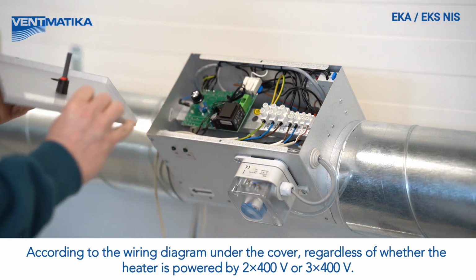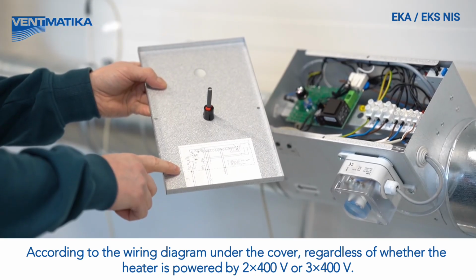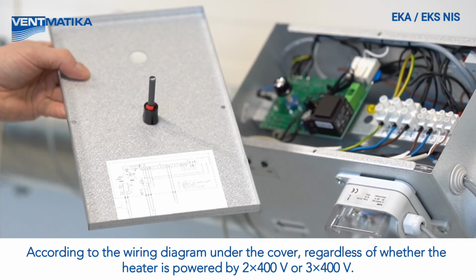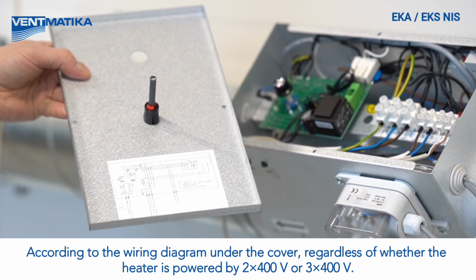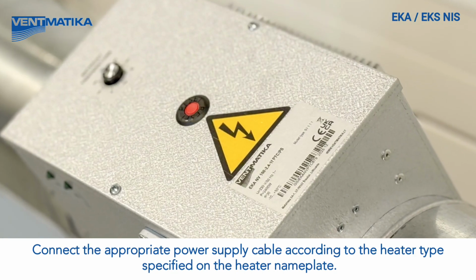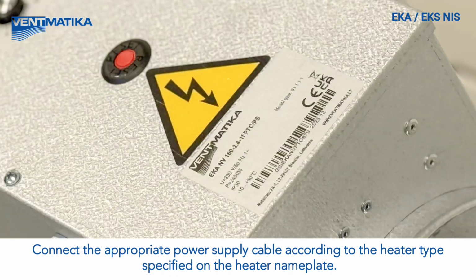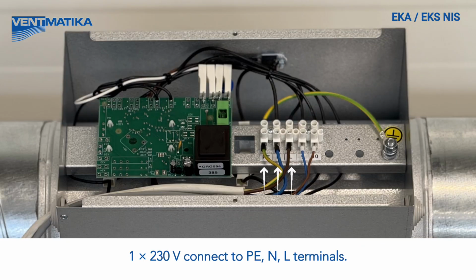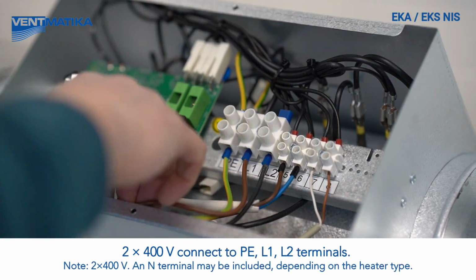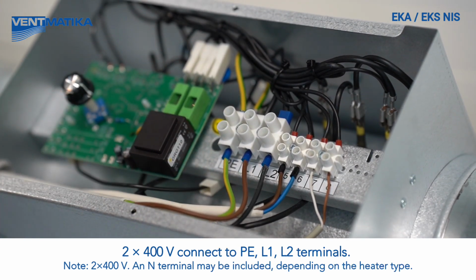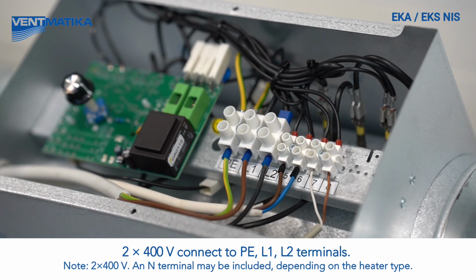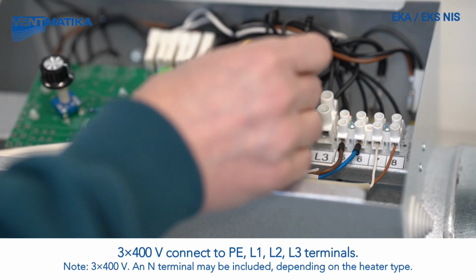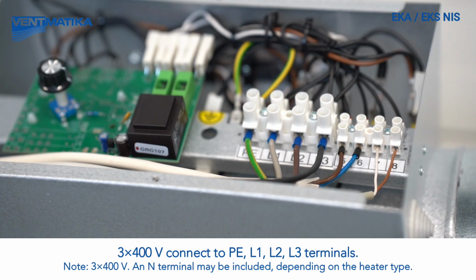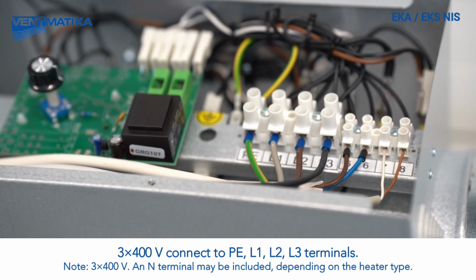According to the wiring diagram under the cover, regardless of whether the heater is powered by 2 times 400 volts or 3 times 400 volts, connect the appropriate power supply cable according to the heater type specified on the heater nameplate. 1 times 230 volts connect to PE, N, L terminals. 2 times 400 volts connect to PE, L1, L2 terminals. 3 times 400 volts connect to PE, L1, L2, L3 terminals.